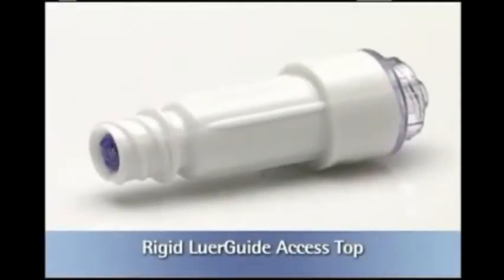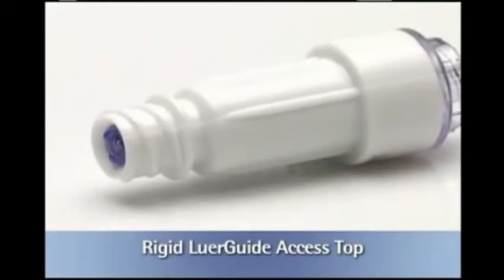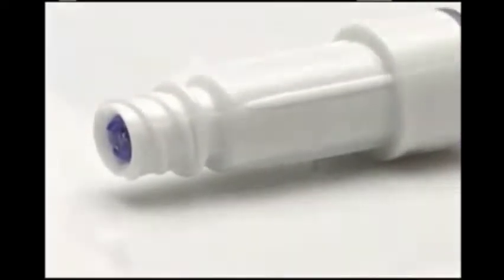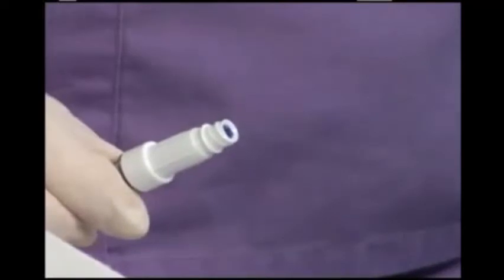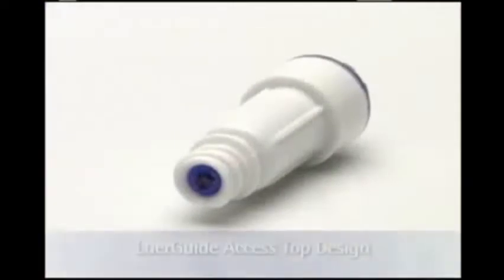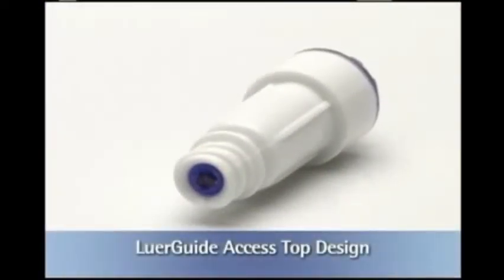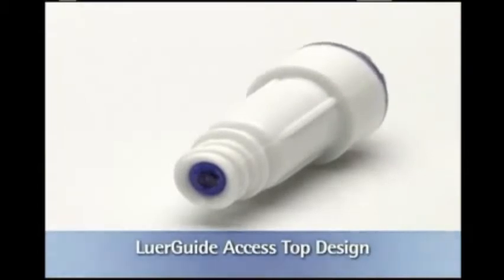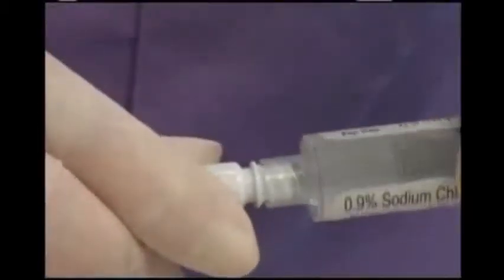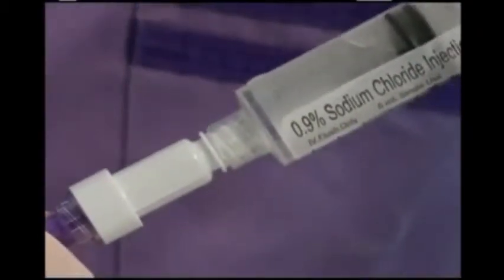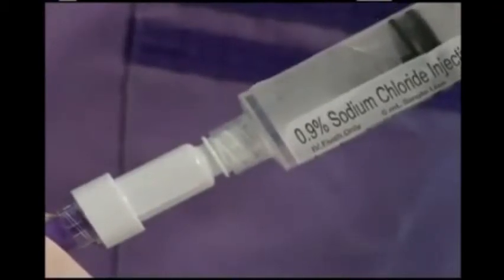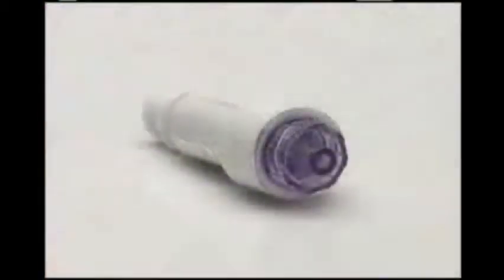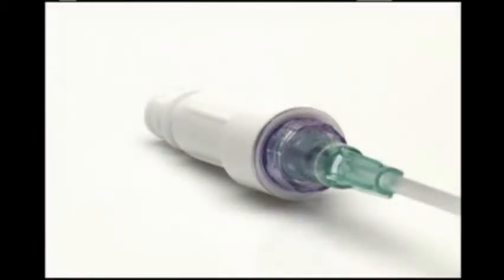Ultrasite is a one-piece needle-free Luer access device with a rigid Luer guide access top that does not allow for needle access. This helps enforce compliance and reduce needle stick injuries. The Ultrasite Luer guide access top with an external seal reduces the risk of unintentional touch contamination. The Luer guide design makes connection easy by guiding the Luer taper into place. This design reduces potential slippage of the syringe during connection. The male Luer lock connector attaches securely to the IV catheter line or extension set.